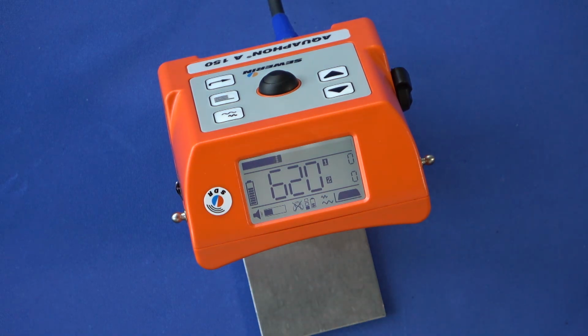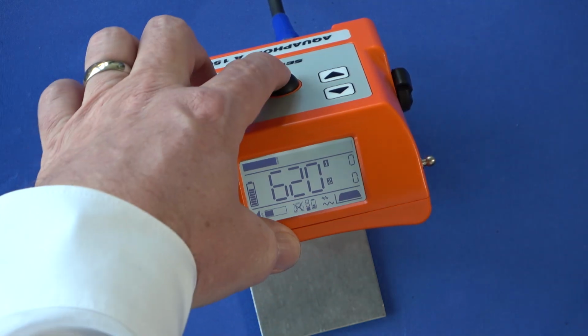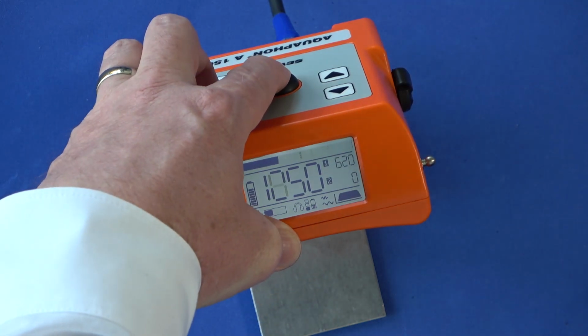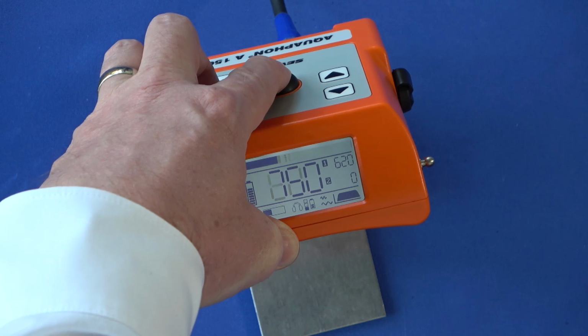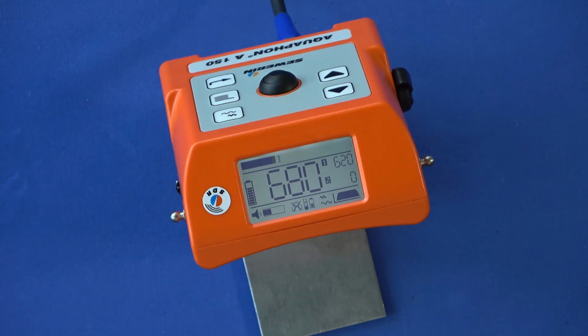In the center of the screen you can see the measured minimum noise level. The measurement starts at 1999 and it is reduced until the minimum noise level is reached. The minimum level describes the most quiet moment of a measurement. In an ideal case, at such moment only the noise of the leak is present. Releasing the activation button stops the measurement.